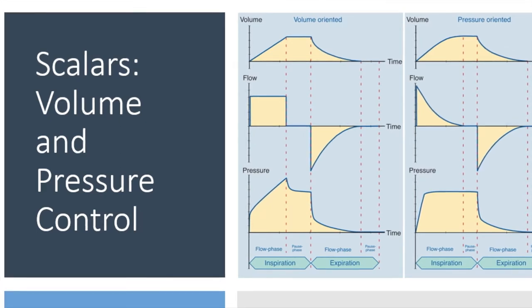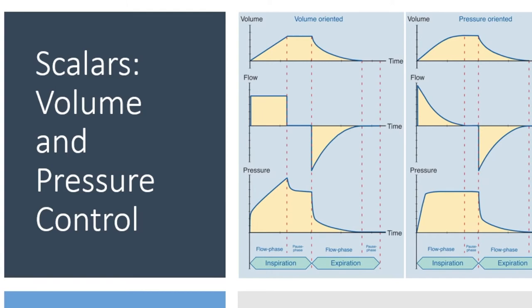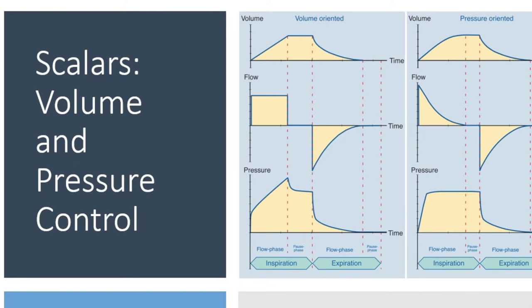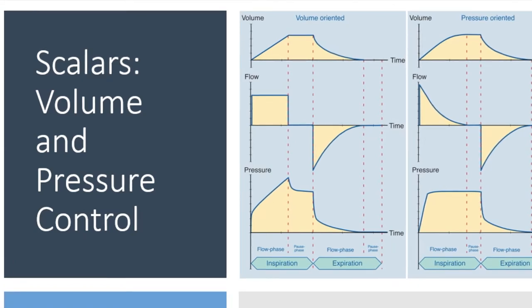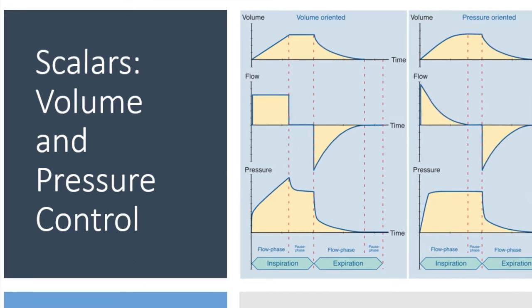The volume scalar is not as informative as the other two, but worth a quick look. On a volume-style breath, the continuous flow going in means volume increases, then at plateau pressure — where there's no flow — the volume plateaus, and then drops with expiration. On the decelerating flow breath, volume gradually increases even as flow decelerates, but the rate at which it increases drops off and flattens, then there's a period of no flow — no increase in volume — before cycling into expiration.